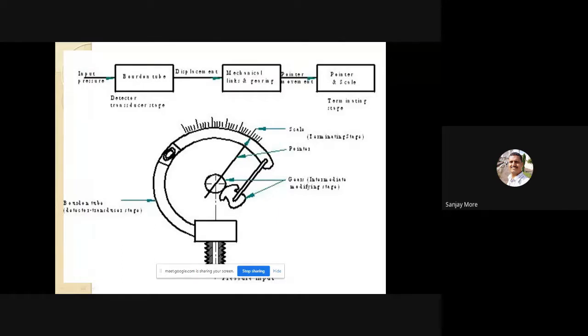So when static pressure is applied to the Bourdon tube here, and its free end, this is the free end, deflects with a deflection which constitutes a secondary signal, is very small and needs to be made larger for display and reading. When applying air pressure here, this air goes to this free end, and the free end is connected to the rack and pinion arrangement, and this rack and pinion arrangement is connected to the pointer. When you are applying pressure on this tube, this rack and pinion arrangement, this pointer moves slightly. Okay. The task is accomplished by an arrangement of lever, quadrant, gearing and pointer. Here the gear arrangement is there. Then the amplified displacement constitutes the tertiary signal which is indicated by movement of the pointer against a graduated scale.